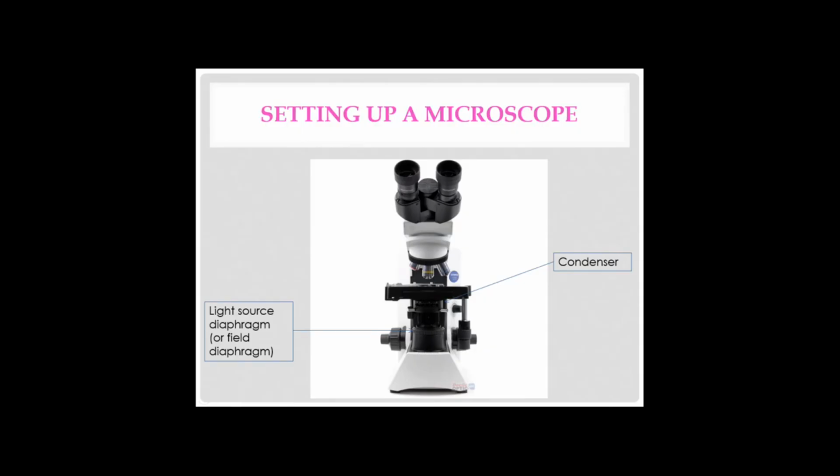If you lower the condenser, the light will be refracted and the angle of the light cone will be increased. This will increase the refraction of the cell borders. This is useful, for example, if you wish to examine urine, a slide agglutination test, or any other form of wet preparation. You can shut the diaphragm of the condenser and lower it, which will make the cell borders easier to see. But in cytology, we do the opposite. You move the condenser up and open the diaphragm to the maximum.